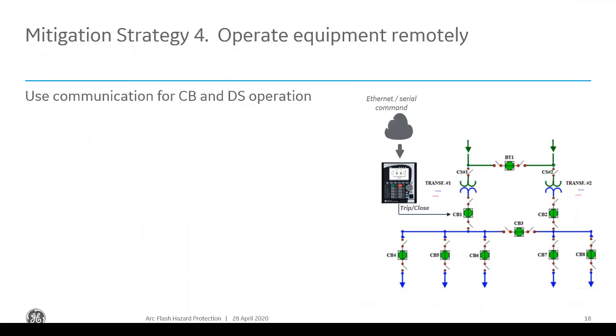Modern protective relays, microprocessor-based relays, have extensive communication and control capabilities that can be used for remote operation, like closing and opening the switching devices. To be exposed to arc flash energy, you have to be in front of the equipment or in the vicinity of the equipment where the arc flash energy exposure is. So you want to stay out of that area. That's the most mitigating factor: if you stay out of that area, you're not going to be exposed to the hazard. So controlling and operating breakers remotely is a very effective way of doing this.